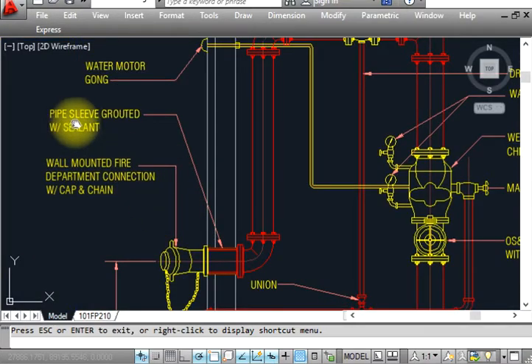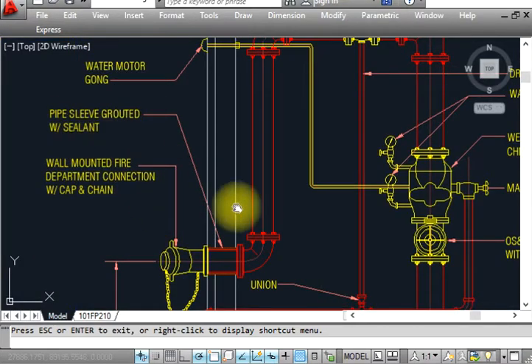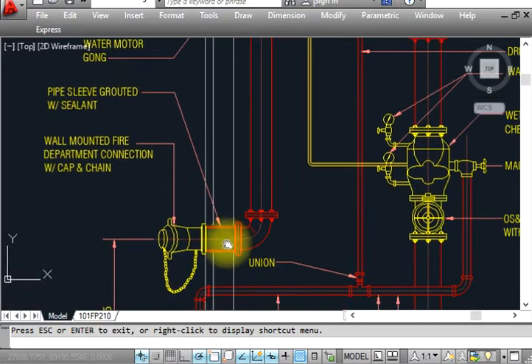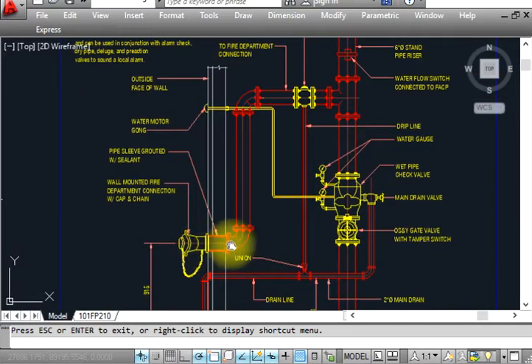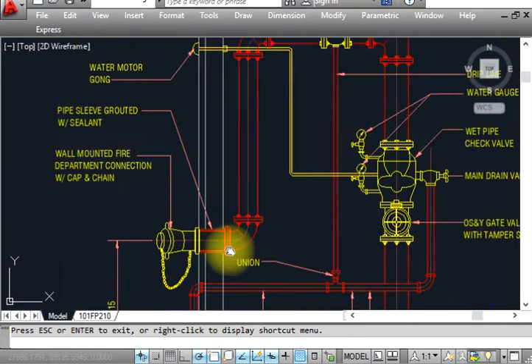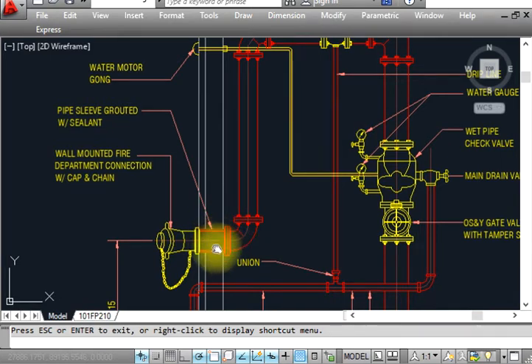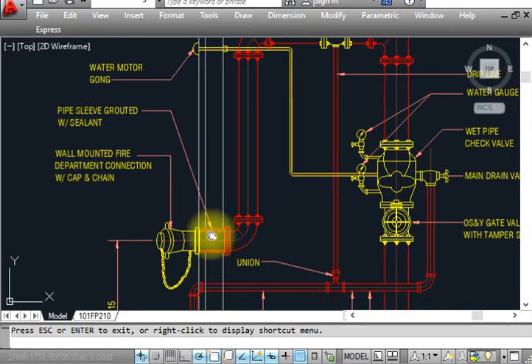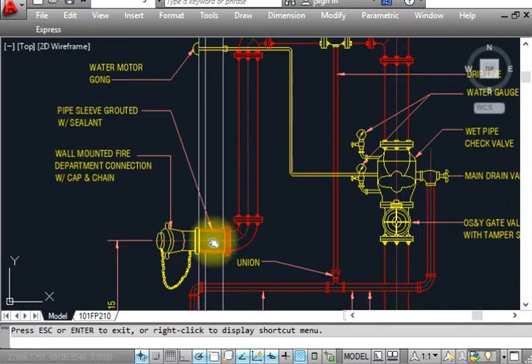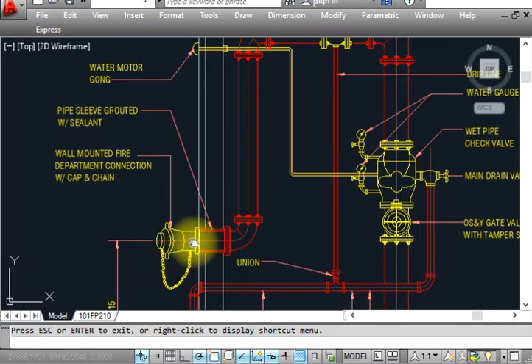This is a pipe sleeve grouted with sealant, because here the pipe is passing through the wall, so we have to provide a sleeve. Whatever the diameter of the pipe, the sleeve should be two inches, which is 50mm, and will be 50mm more at least.